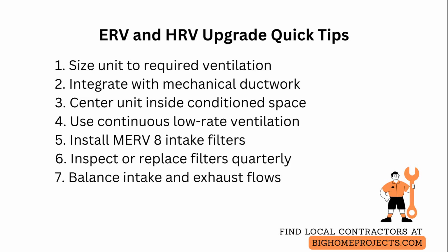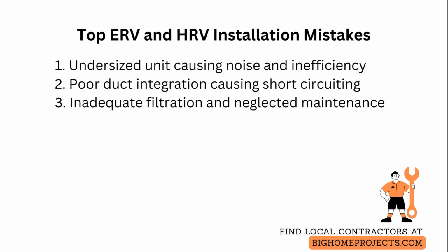Common mistakes include selecting an undersized unit and then running it at high fan speeds, which increases noise and energy use. Remedy that by recalculating needs and choosing a properly rated model, and by preferring 2-speed or variable speed fans for quiet, continuous operation.